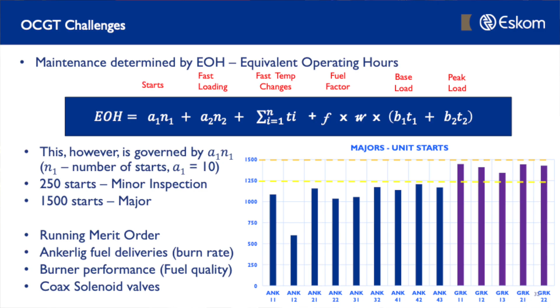With the stop-start operation, we see issues with moving parts like the coax solenoid valve, which regulates the fuel flow - we have to replace them much sooner than needed, and it's very expensive. We've been seeing issues with burner performance, where the burners were clogging. We contacted the OEM but didn't get much help resolving it, except replacing the burners. So we looked at innovative ways to handle it. There's an opening of 0.7 millimeters where the fuel sprays out, and amazingly, a dental drill can actually be used to open up that area. We've been using that to maintain the units until our next major outage - things like that we have to do to keep our units running.